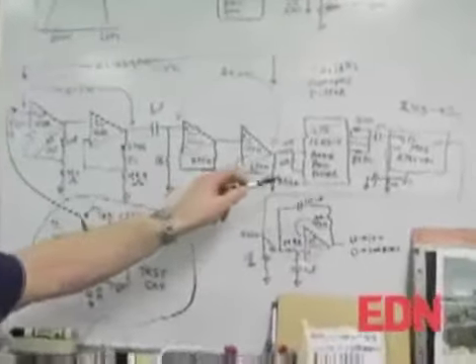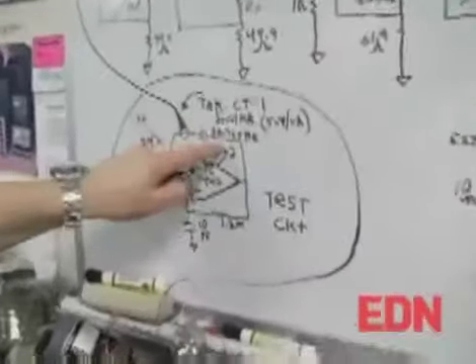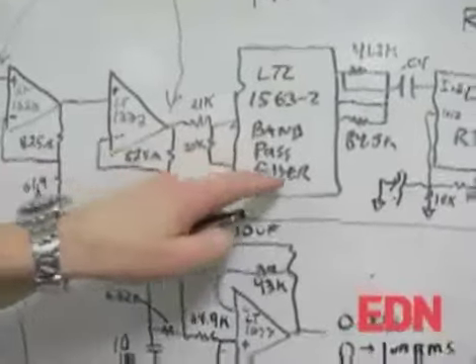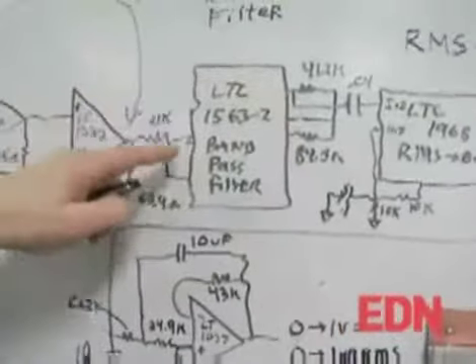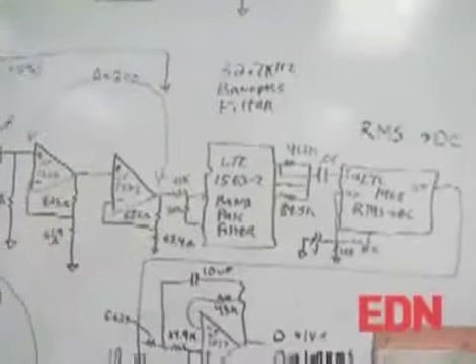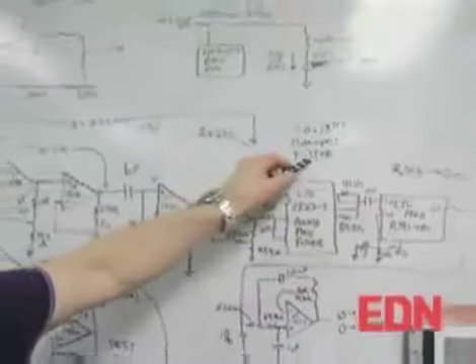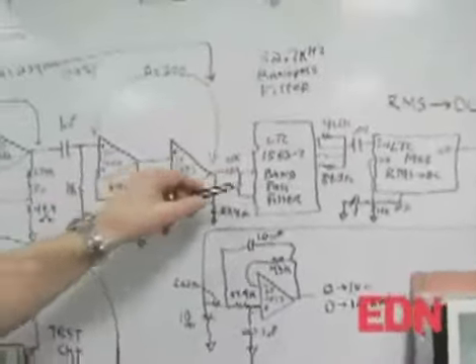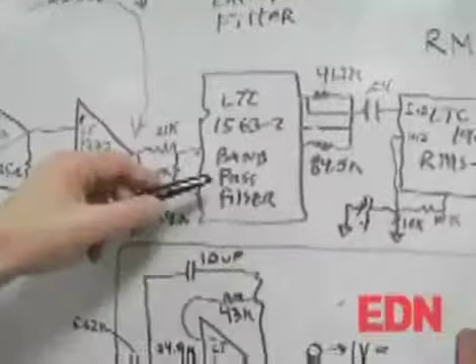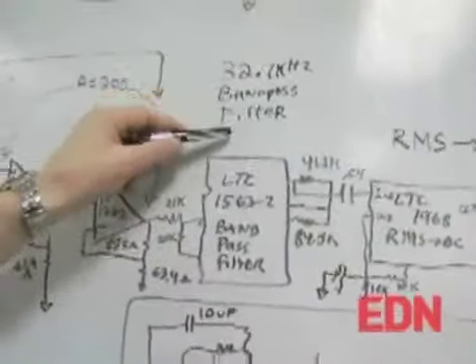Up to this point, the entire gain chain is broadband. Now what I want to do is take advantage of the fact that I'm operating at one frequency and one frequency only and narrow band the amplifier. To do that, we run through this 1563-2 bandpass filter centered at 32.7 kilohertz. The slopes are very steep on this—approximately 20 dB attenuation either side of 32 kilohertz. What that does is it just kills the noise in the measurement for us. The gain of this at the peak of the bandpass is unity.